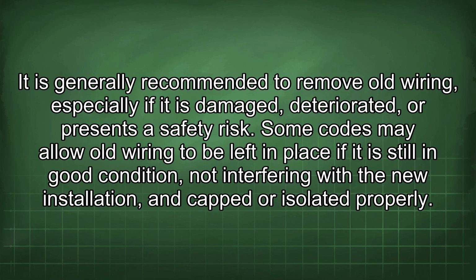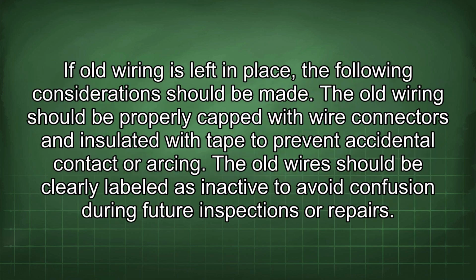Some codes may allow old wiring to be left in place if it is still in good condition, not interfering with the new installation, and capped or isolated properly. If old wiring is left in place, the following considerations should be made. The old wiring should be properly capped with wire connectors and insulated with tape to prevent accidental contact or arcing. The old wires should be clearly labeled as inactive to avoid confusion during future inspections or repairs.